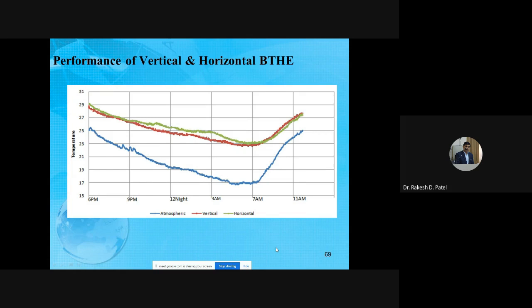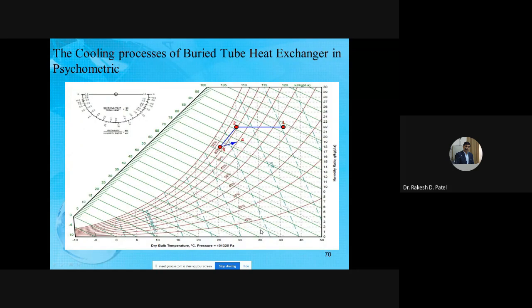Only one limitation of both heat exchangers is the space. If you have a lot of space for the installation, you can easily install the horizontal heat exchanger. And if you are constrained for space, then you go for the vertical heat exchanger. So only space, I think, is a limitation between the horizontal as well as the vertical heat exchanger.